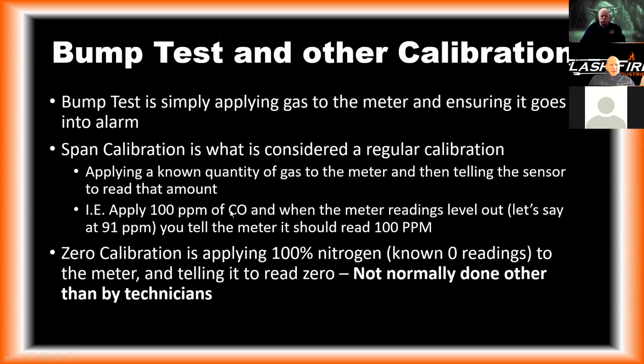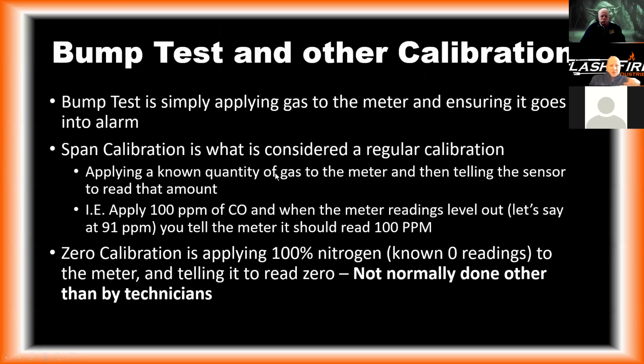I'm not going to get into these too much because this isn't what you guys are doing on the line, but a bump test is just testing the meter, making sure that it goes into alarm. Span calibration is what we're actually, when you say calibrate the meter, that's what you're doing. Span calibration, you're actually making the meter read a specific gas to a specific quantity, saying, okay, this is what you should read. Think of calibration as like making sure your speedometer is reading correctly.